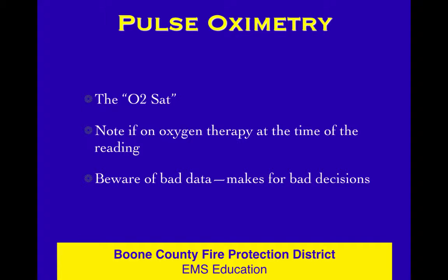But that's not what it's on there for. The pulse oximeter has a heart rate indicator on it in order for you to verify the validity of that pulse ox reading, not for a quick, easy, cheap, lazy guy's way to check the heart rate. And it has become a shortcut that's really kind of silly.